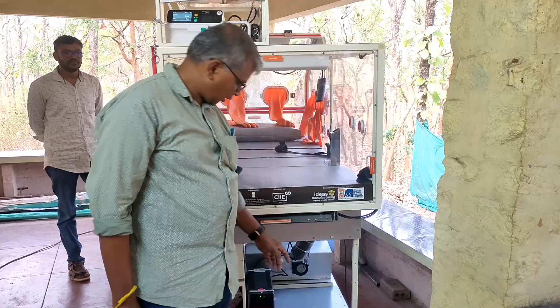There are 2 buttons here. One is a momentary suction, the other one is a continuous suction. Both are supported here. We have an inbuilt UPS with a 2-hour battery backup for the entire equipment. The UPS is not designed to run the AC. Without the air conditioner, the fan will be running, but the rest of the medical equipment will be running for 7 hours, because all the medical equipment we have chosen has an inbuilt 5-hour battery backup on its own.